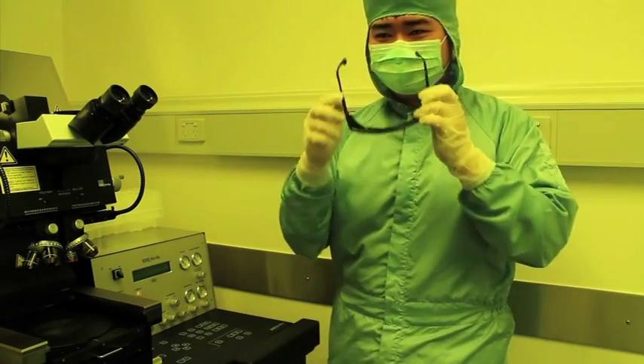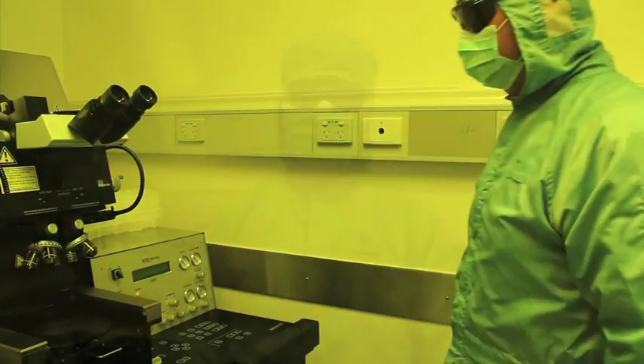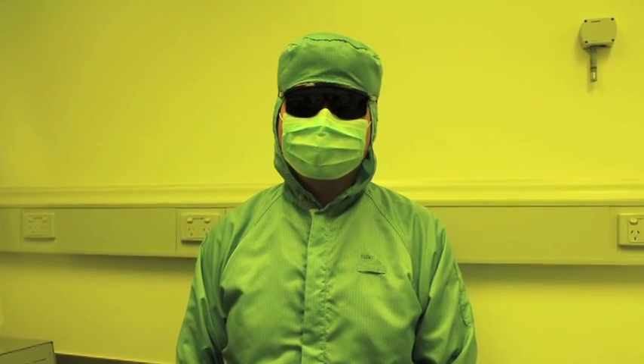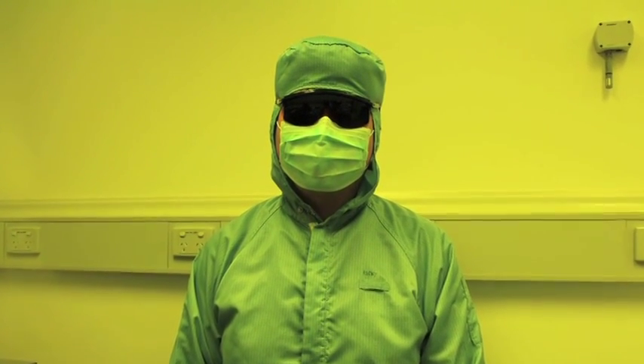There are several hazards associated with the mask aligner. The exposure lamp emits high energy ultraviolet light which can cause severe eye damage and skin burns. Do not look directly at the UV lamp during exposure unless wearing the correct UV safety glasses.